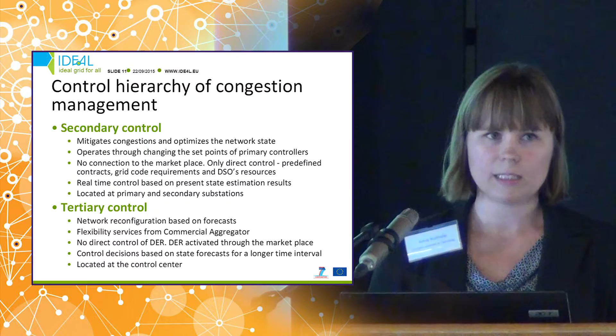Then we have the tertiary controller that operates on the control center level. Its control actions are based on forecasts for a longer time period, and it has several parts. It has a network reconfiguration algorithm that calculates the optimal network switching state for the next 24 hours, and it is also responsible for interactions between the TSO and the marketplace. It doesn't control the distributed energy resources directly, but it utilizes the marketplace for this control.